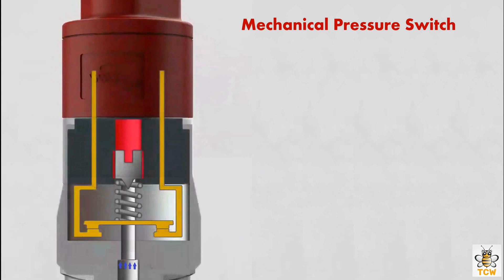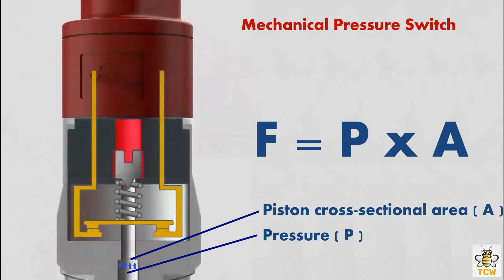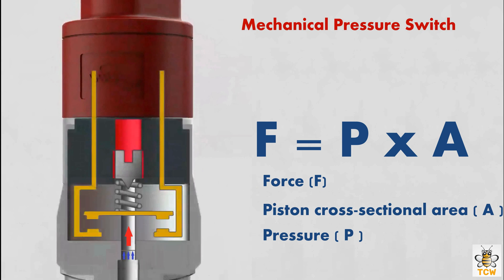When the piston on the pressure switch receives pressure from the outside — where the pressure is symbolized by the letter P — the pressure P acts on the piston with a cross-sectional area of A. According to the law of physics, there will be a force F where F equals pressure P times cross-sectional area A. This force F compresses the piston held by the spring so the piston lifts up. The raised piston separates the contact surfaces of the switch and breaks the electrical circuit.